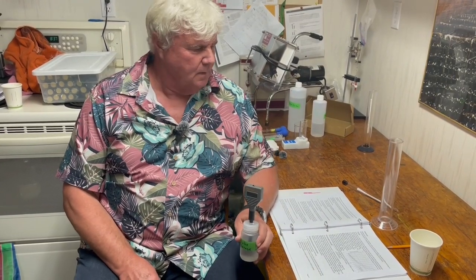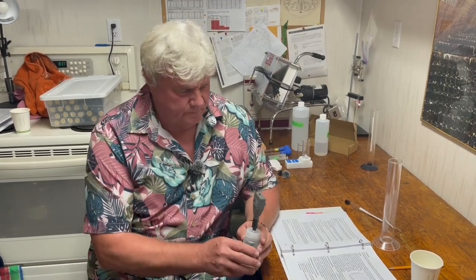So this is your basic cheapo pH meter, or pH pen as they call them. I keep this in a probe storage solution, which helps keep the electrode properly hydrated. If you let them dry out, they'll fail a lot earlier than if you don't. If you keep them in here, they last a long time—this one's probably 10 years old. These are about $20 or $30 online, so they're not that expensive.